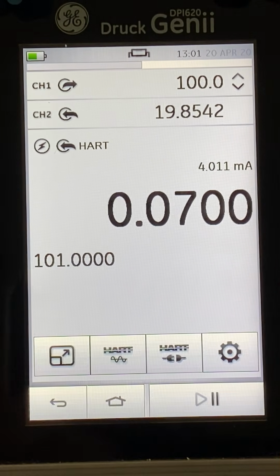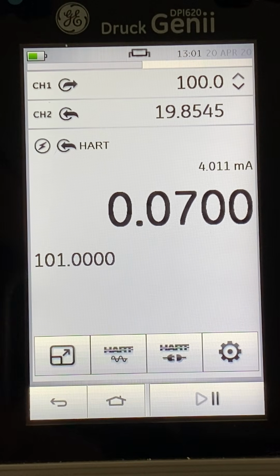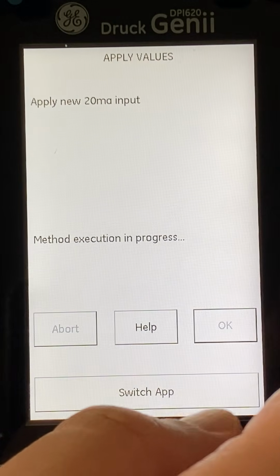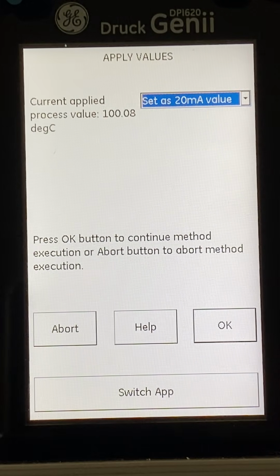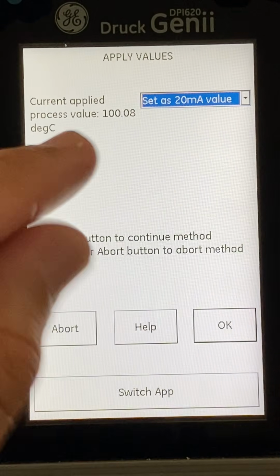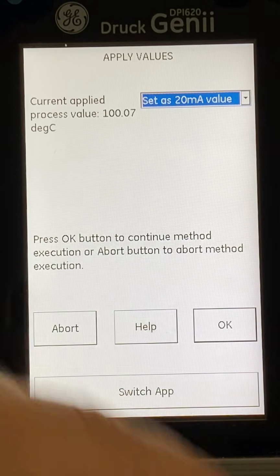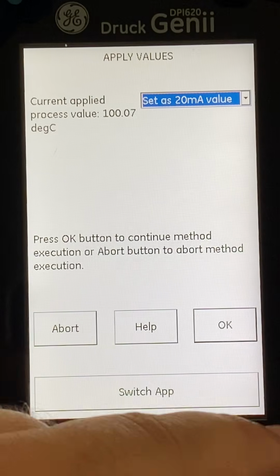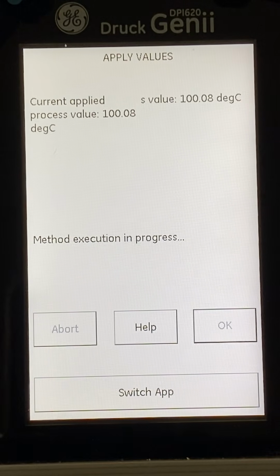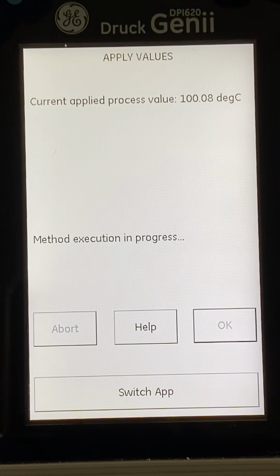As we can see, it's now set to give 19.85, but after we adjust that, we apply that. So it's 100.08. So there is a trim here, as you can see. There is a deviation of 0.07 here. That was the error in the transmitter.